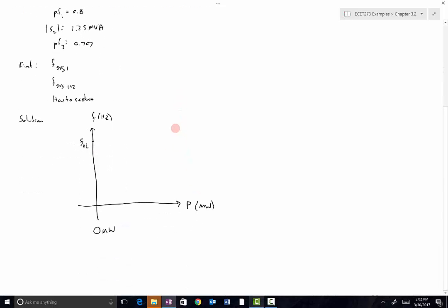61.0 Hertz is telling us the operational frequency of the generator, or its electrical frequency, if it's not providing any power. Sometimes that's called the set point. Typically we have different ways to adjust the prime mover that moves this set point up and down the F axis, and that's how you control the power that a generator is going to supply at 60 Hertz. And F no load is always higher than 60 Hertz in American power systems.